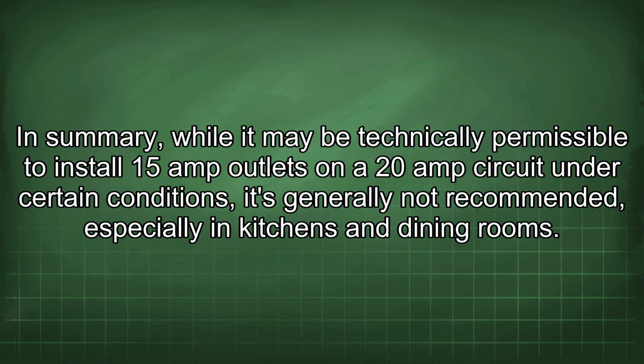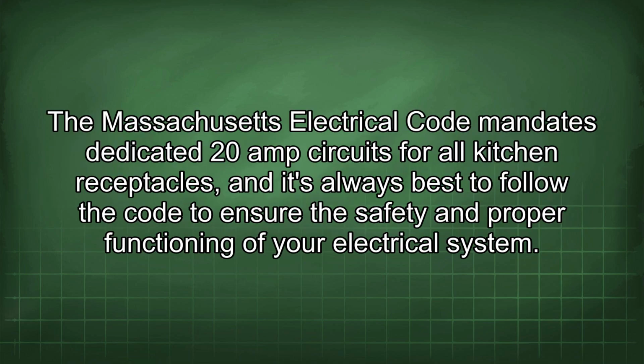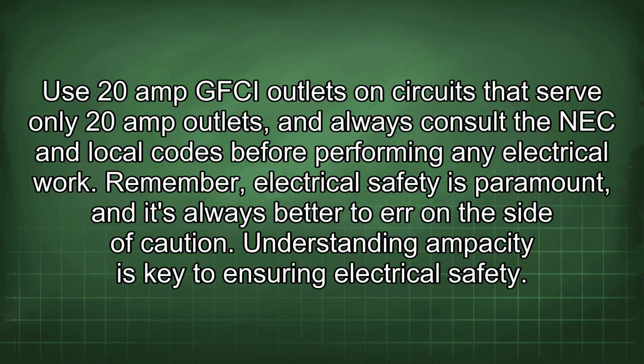In summary, while it may be technically permissible to install 15 amp outlets on a 20 amp circuit under certain conditions, it's generally not recommended, especially in kitchens and dining rooms. The Massachusetts Electrical Code mandates dedicated 20 amp circuits for all kitchen receptacles, and it's always best to follow the code to ensure the safety and proper functioning of your electrical system. Use 20 amp GFCI outlets on circuits that serve only 20 amp outlets, and always consult the NEC and local codes before performing any electrical work. Remember, electrical safety is paramount, and it's always better to err on the side of caution.